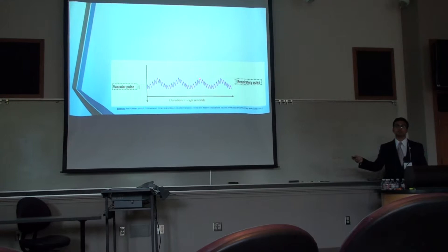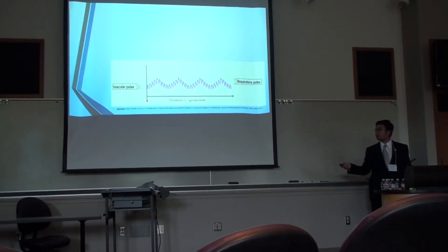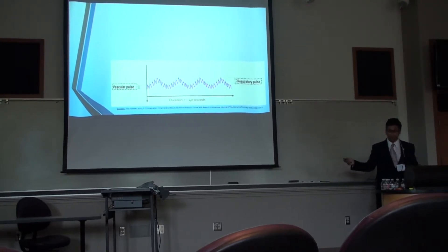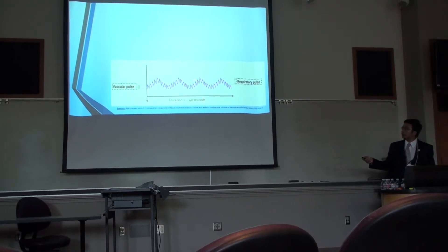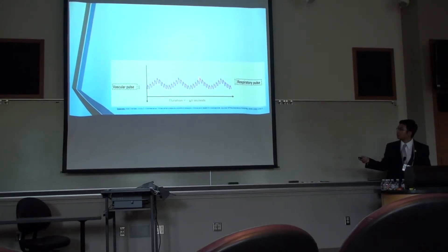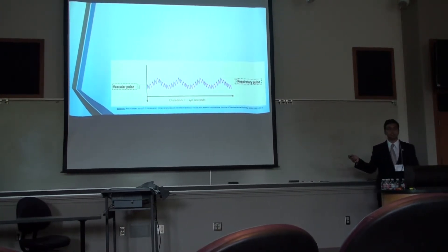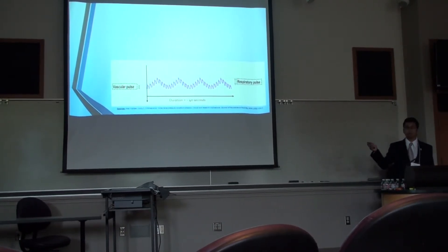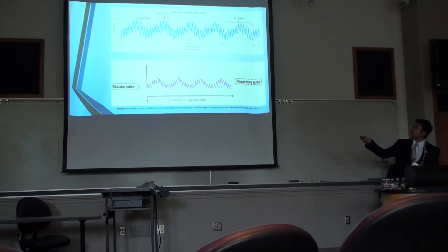This is taken right out of the literature. This is what physiological ICP looks like over a short time course of 40 seconds in a person who is breathing and whose heart is beating. When I first looked at this, I asked myself what it is about this that I need to replicate in my testing system. There are, first of all, the cardiac pulses — each one of these little blips right here is a pulse in ICP that corresponds to one beat of the heart. About four or so of these correspond to a respiratory pulse, and these big waves and troughs are what are known as slow waves. They're idiopathic but physiologically expected. I input this into LabVIEW, had my speakers recreate the scenario, collected the data, and this is what I got.